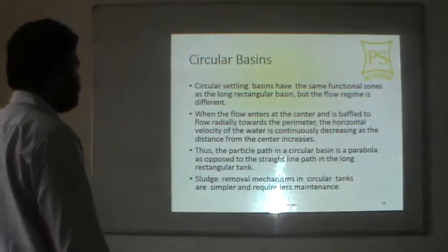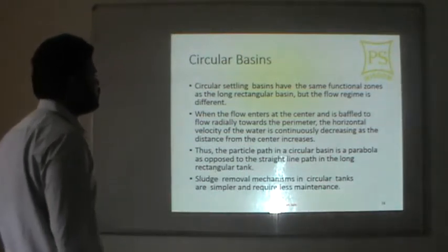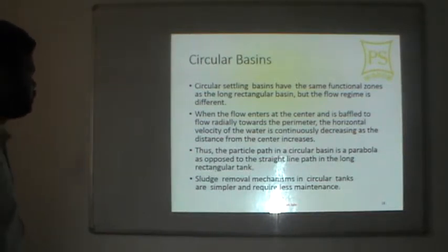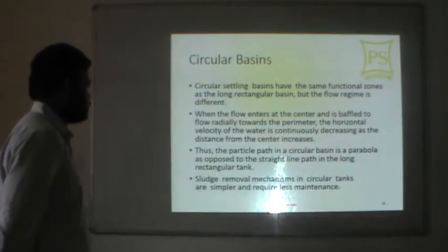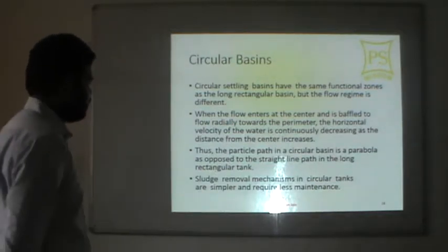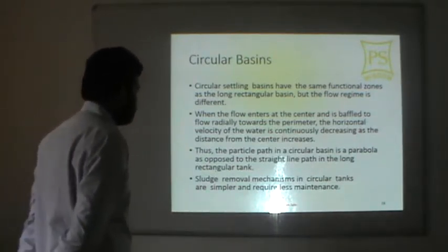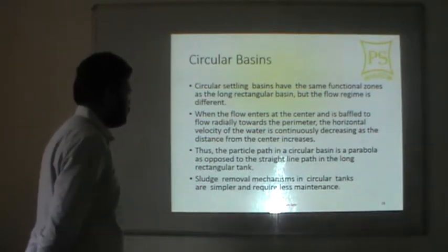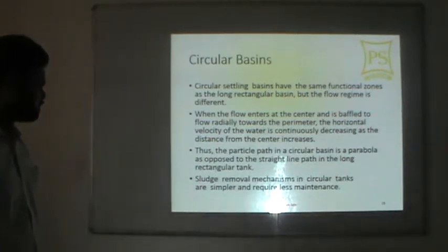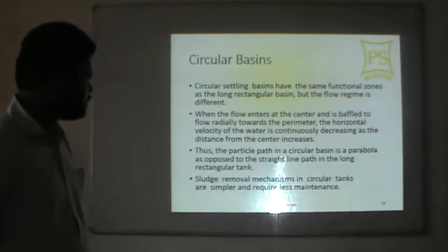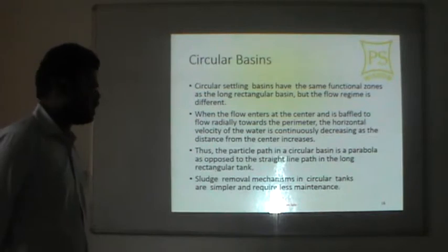Circular settling basins have the same functional zones as long rectangular basins, but the flow regime is different. When flow enters at the center and moves radially towards the perimeter, the horizontal velocity of the water continuously decreases as the distance from the center increases. The particle path in a circular basin is curvilinear, as opposed to the straight-line path in a long rectangular tank. The sludge removal mechanism in circular tanks is simpler and requires less maintenance.